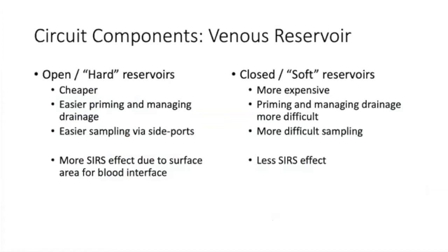Venous drainage flows to a venous reservoir. There are open and closed — or hard and soft — reservoirs. Hard reservoirs are easier for priming and bedside management but have more of a SIRS effect, as all SIRS effects related to cardiopulmonary bypass involve blood contacting non-endothelialized surface area. There is more surface area effect with an open reservoir. Soft reservoirs are more difficult to manage from a perfusionist standpoint but offer less of a SIRS effect and likely some patient benefit.